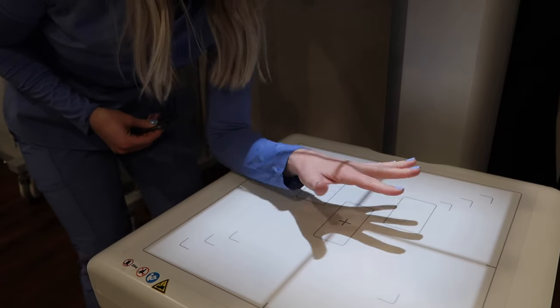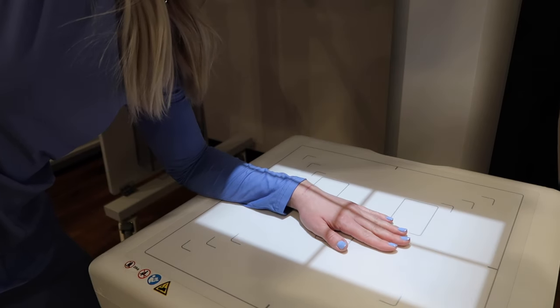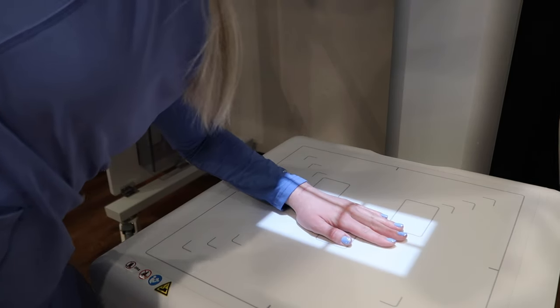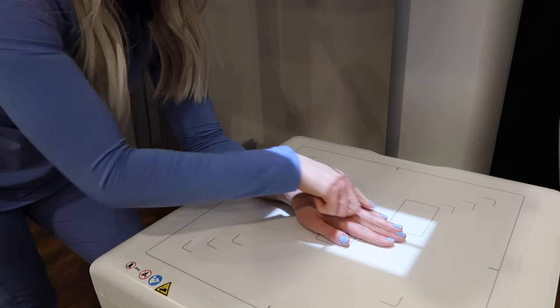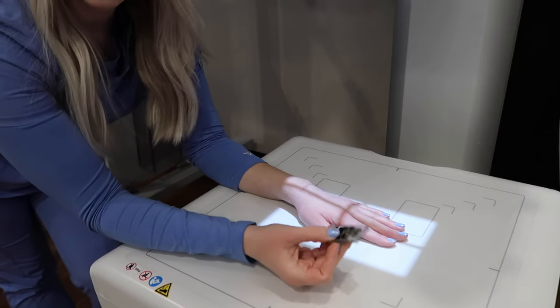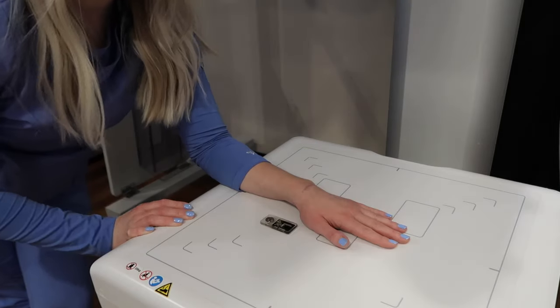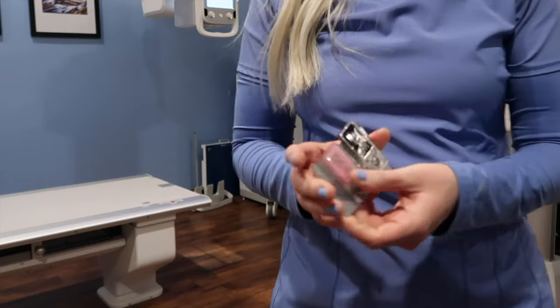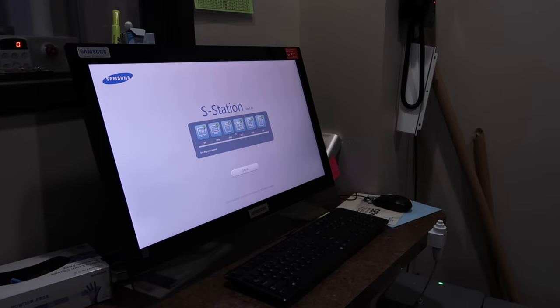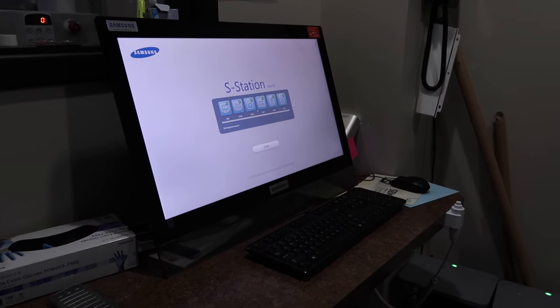This is my light field — this is where I'm actively exposing the patient. If I'm doing a hand X-ray, I don't need to expose the whole image receptor. I can collimate — collimating is reducing your image field size to reduce patient exposure and scatter radiation. You want to get clothing artifacts out of the way; my nails could cause an artifact. You also want a marker on your picture — people ask what these are. They mark the left and right side of the body and the initials of the tech. I use rad adhesive, which I like because I can wash it with soap and water.